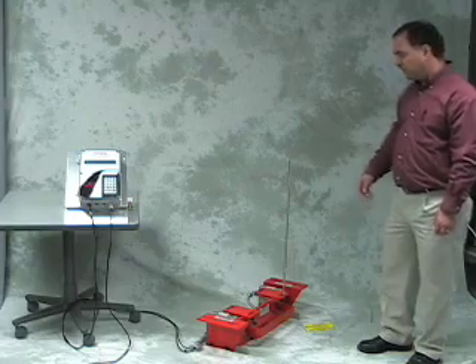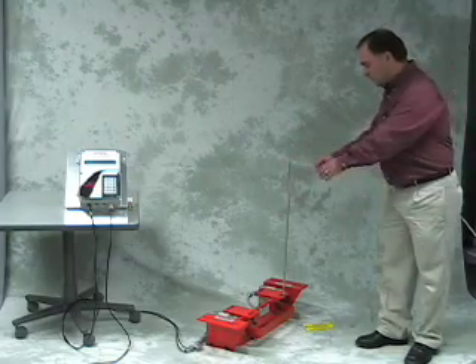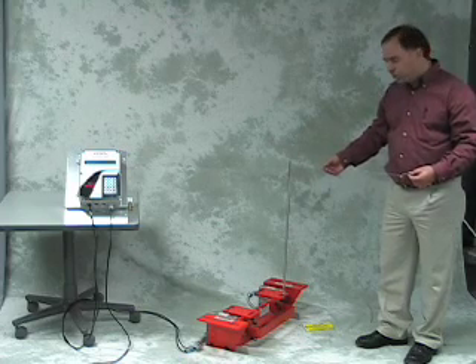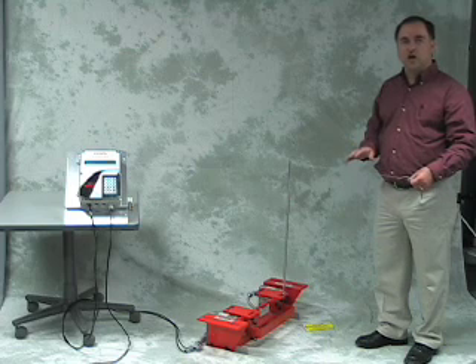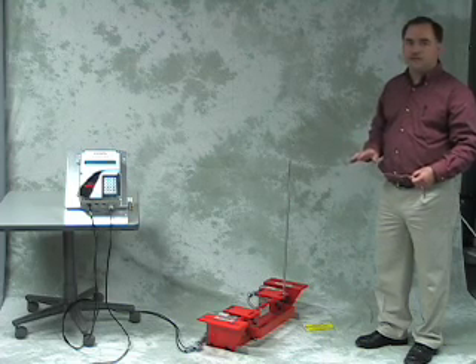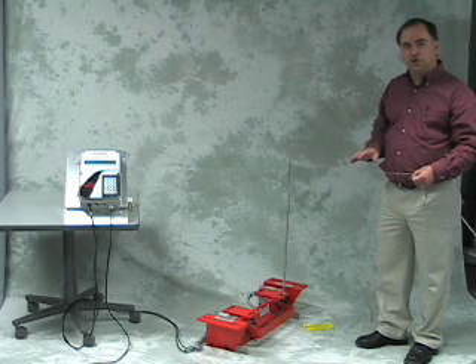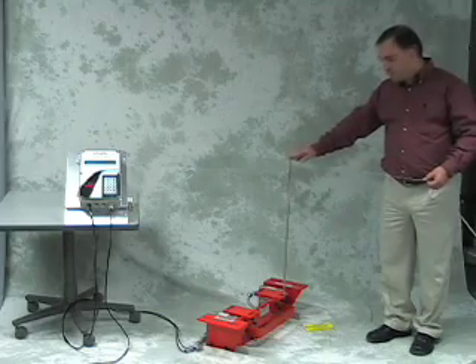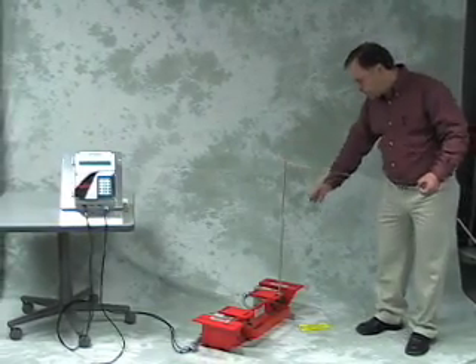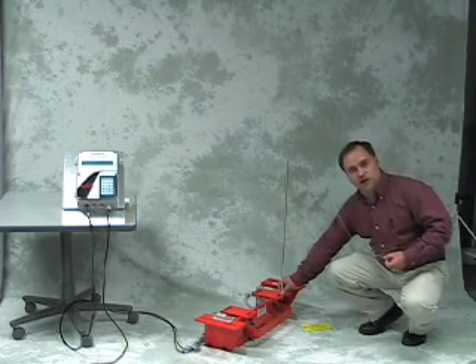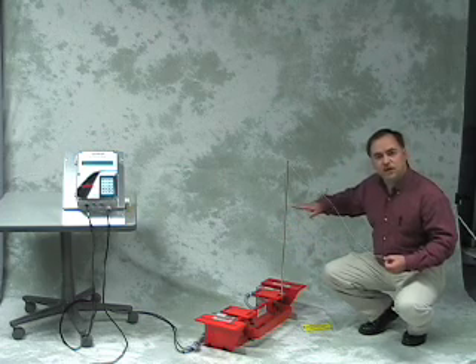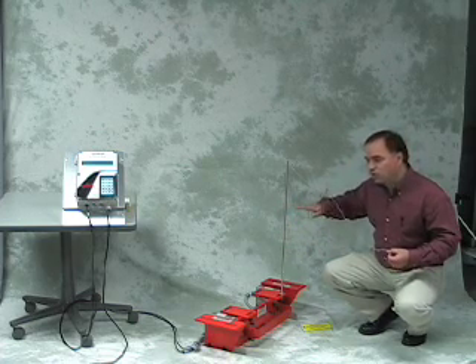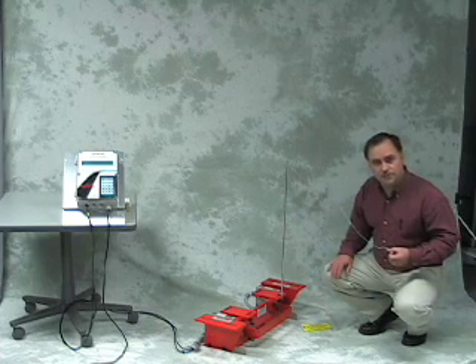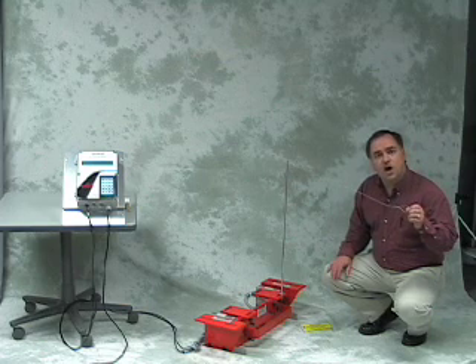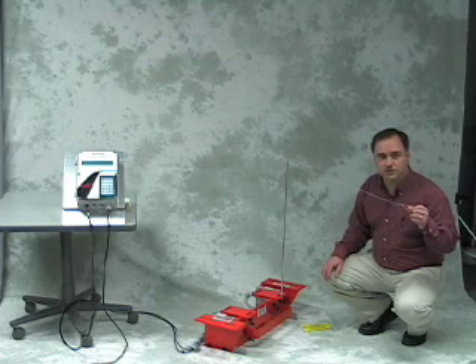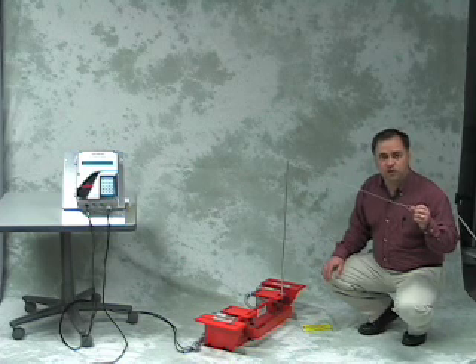Included with the MSI demo kit is a stainless steel rod with a hole drilled in it and a string attached. This shows that horizontal forces on the conveyor have no effect on the load cell reading—an advantage none of our competition can match. The rod threads into the scale where the idler would attach; the idler sits above with a belt running on top, creating horizontal forces on the scale mechanism. Our load cells are impervious to these horizontal forces and only sense the load on the conveyor.